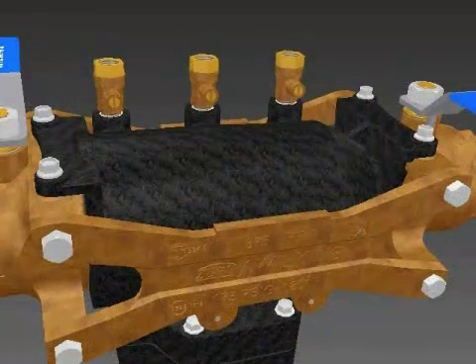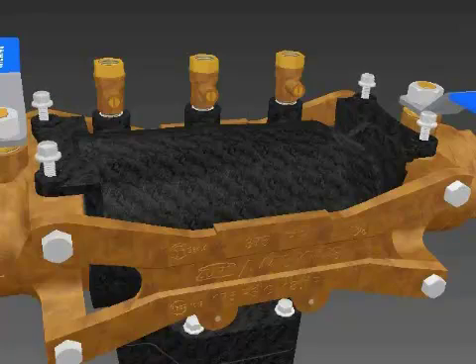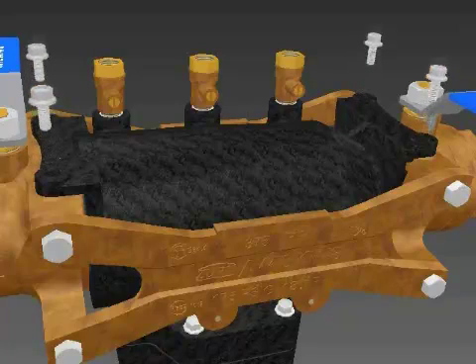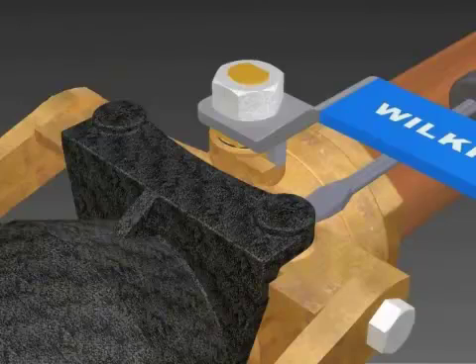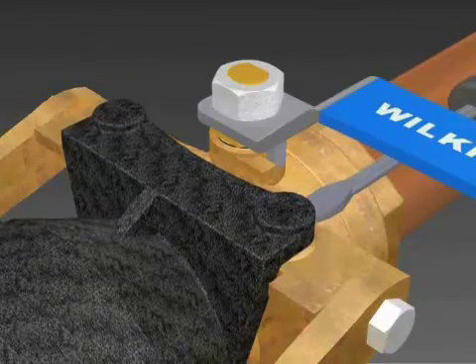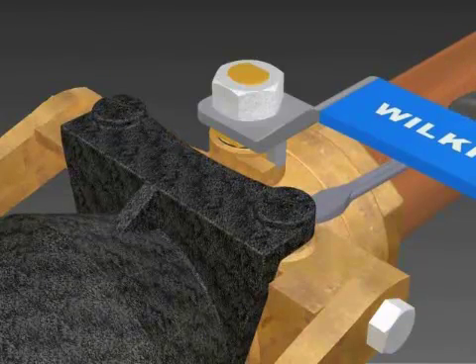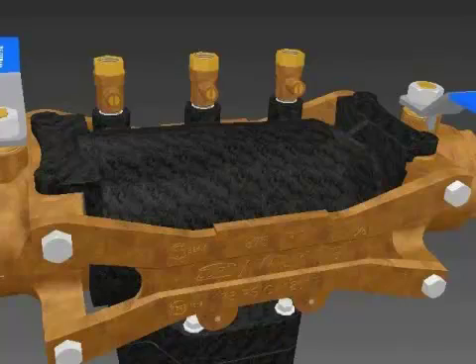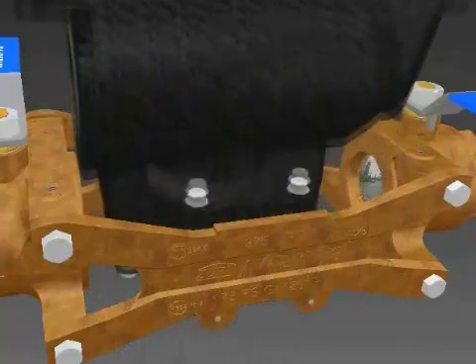Unscrew the four bolts that hold down the black check housing. Insert a flat head screwdriver under the tabs where the bolts were and pry upward to loosen the housing. Next, lift the housing out of the bronze body.